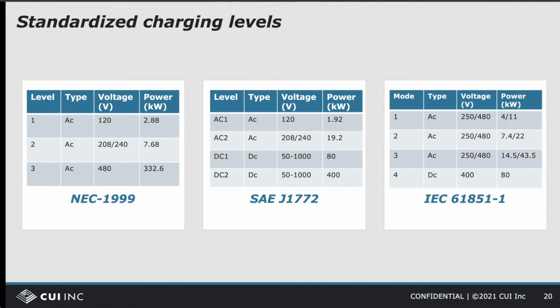The SAE International later defined their own set of levels in their J1772 standard. This standard applies to North America and defines 4 levels. In this standard, DC charging is added and split into 2 separate levels, giving a total of 2 DC and 2 AC charging levels. Internationally, the IEC in their 61851-1 definition defines modes instead of levels, and similar to the SAE standard, it has 4 modes, which include 1 DC mode. The variety of standards can make things a little bit confusing, and perhaps because of that or because it was one of the first classifications of chargers, the original 3-level system seems to have stuck, even though other standards have come about with a different number of levels.